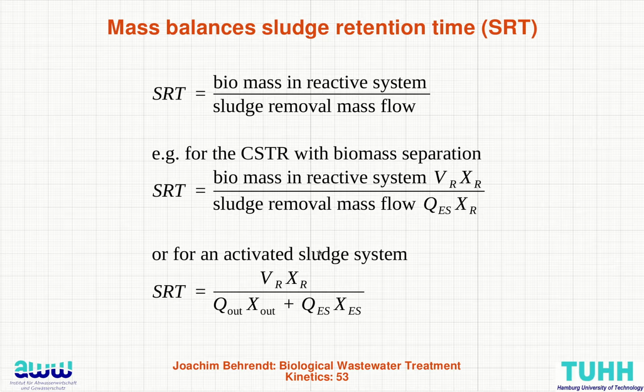Yeah, for an activated sludge system, there we have here a clarifier for the separation of sludge. The sludge retention time is compiled from this formula. For a stationary system or static system, the sludge amount in the reactive system is the same, the mass, but the sludge is removed in the outflow because the clarifier will not separate 100% of the biomass. There are still some grams per cubic meter in the outflow, and of course the excess sludge that we are removing. But these are other concentrations that we don't know yet.